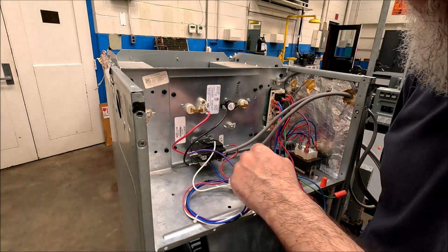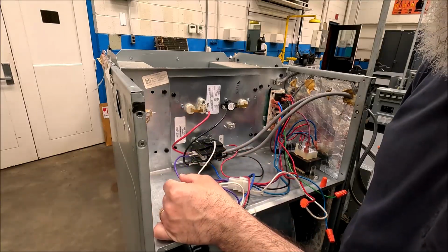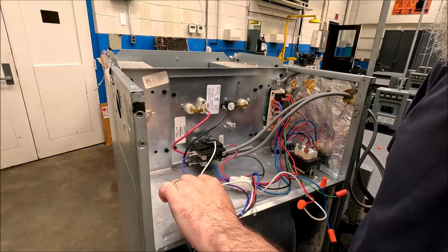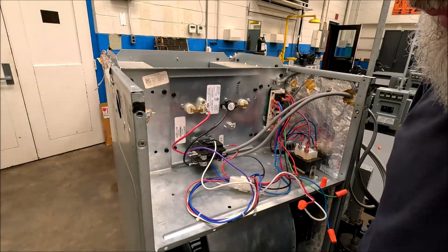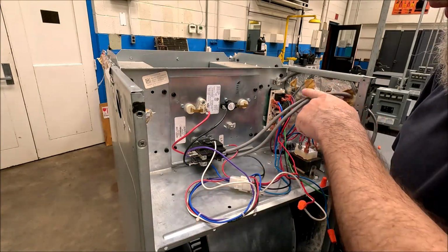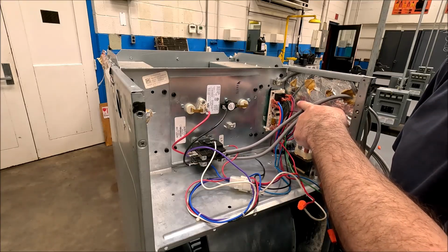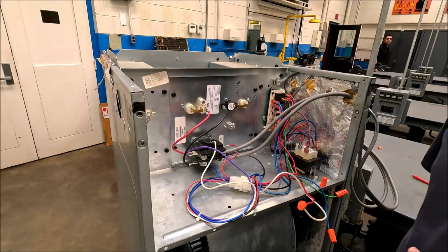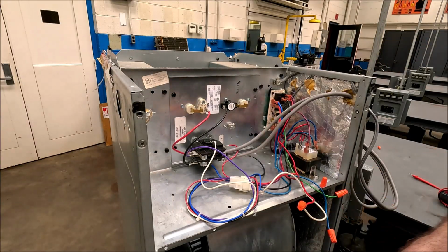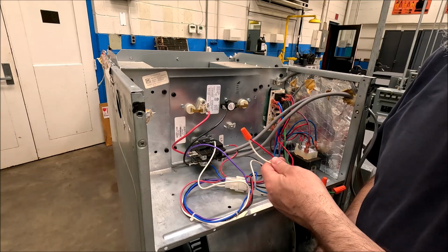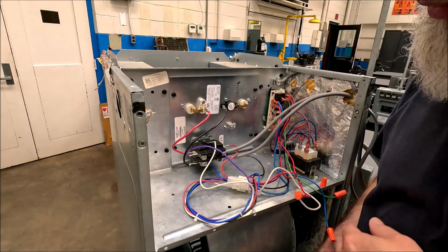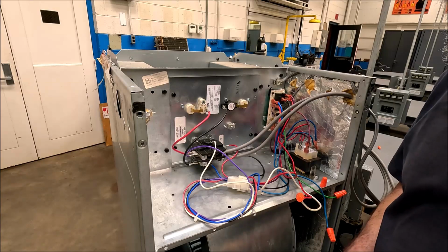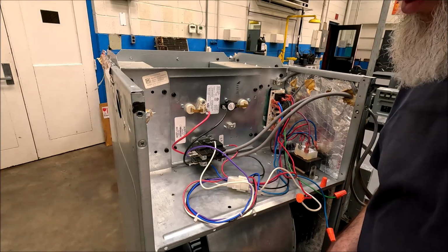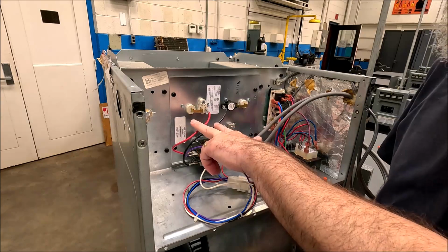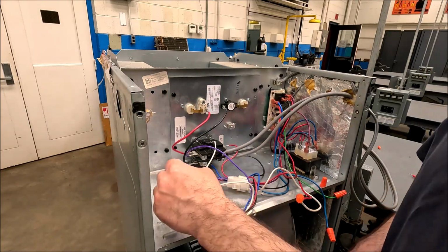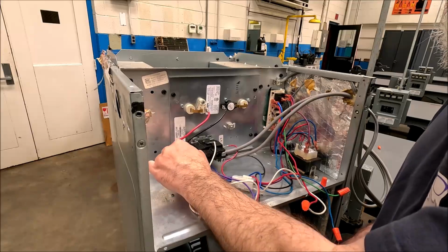And because this is a PSC motor, you're going to have this redundant safety circuit, this purple wire that we already know backfeeds into the blower relay through the normally closed circuit to turn on the PSC motor. So for our purposes here, I'm just going to do red to white and everything's going to click in fine. So it's going to be noisy, the blower's going to come on. But some loads, it doesn't matter which side you check it on. So in the case of the heater, it doesn't matter. Once the heater comes on, I'll disconnect the blower.